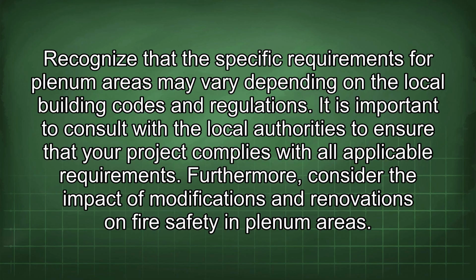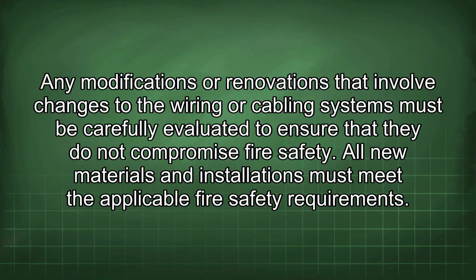Recognize that the specific requirements for plenum areas may vary depending on the local building codes and regulations. It is important to consult with the local authorities to ensure that your project complies with all applicable requirements. Furthermore, consider the impact of modifications and renovations on fire safety in plenum areas. Any modifications or renovations that involve changes to the wiring or cabling systems must be carefully evaluated to ensure that they do not compromise fire safety. All new materials and installations must meet the applicable fire safety requirements.